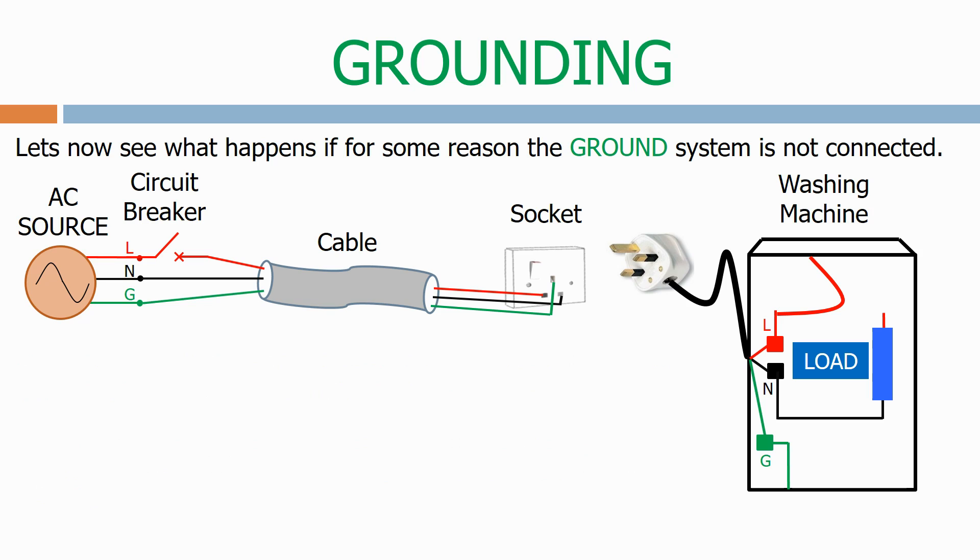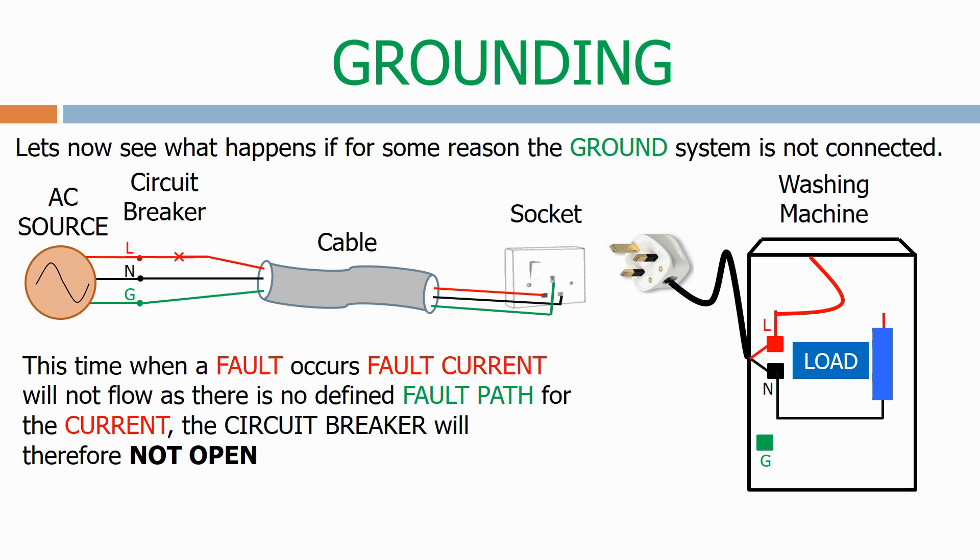Let's now see what happens if for some reason the ground system is not connected. This time when a fault occurs, the fault current will not flow as there is no defined fault path for the current. The circuit breaker will therefore not open.